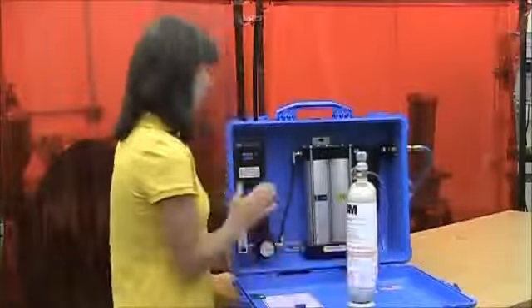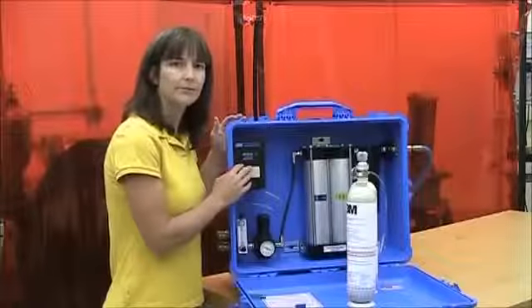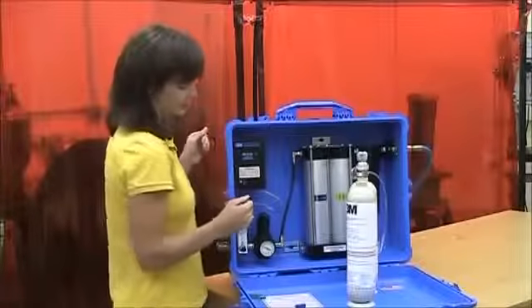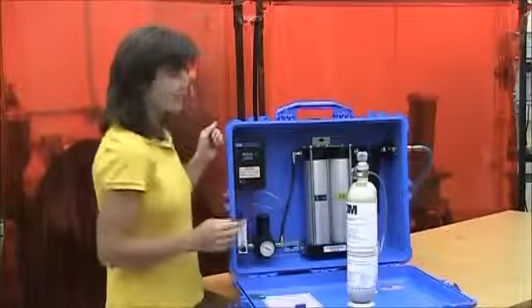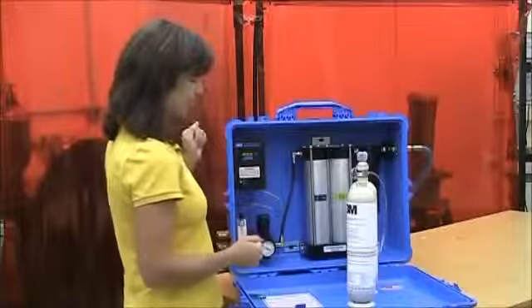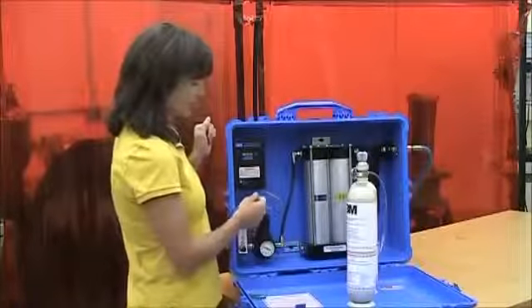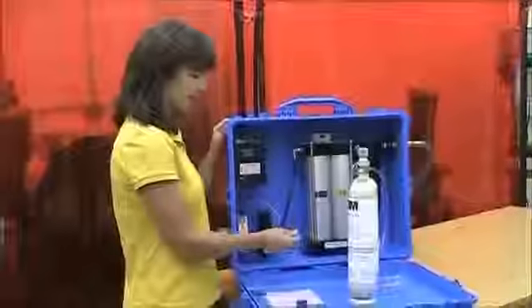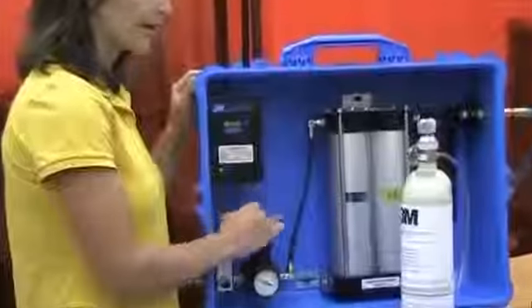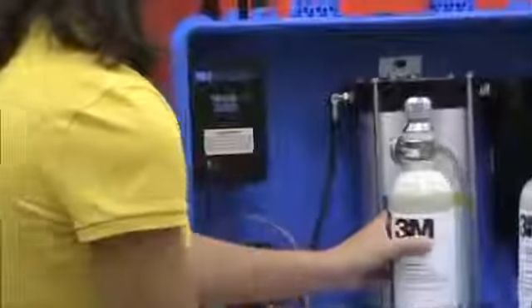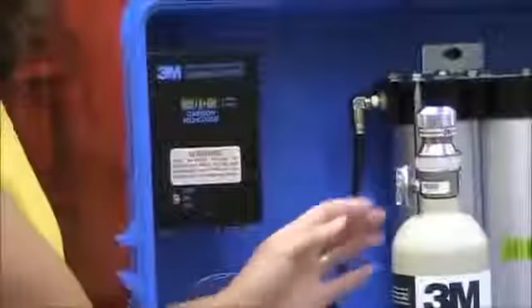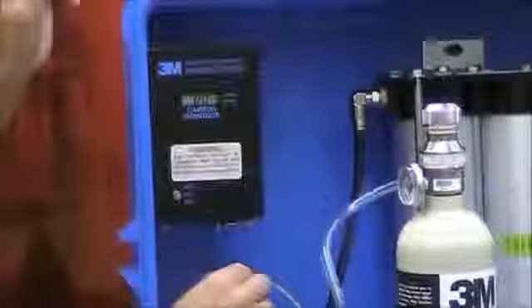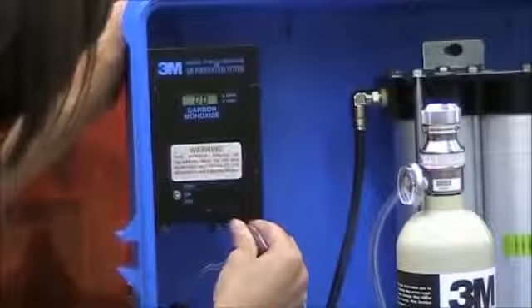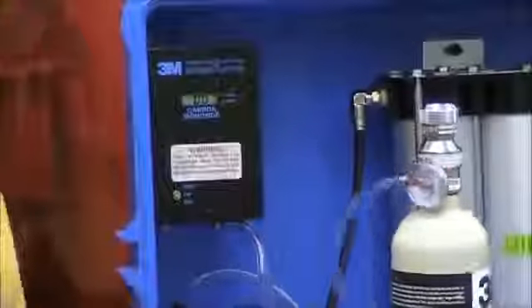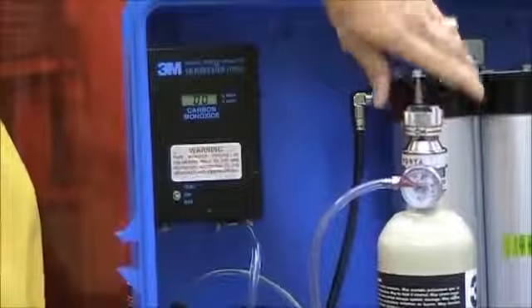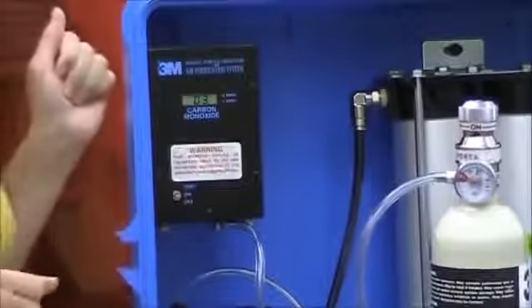You're going to want to make sure that the calibration gas itself is not expired. You also want to make sure your carbon monoxide monitor has been warming up for at least 5 minutes. This will help the calibration go a little bit smoother. Mine's been on for at least 5 minutes, so we'll get started. I'm going to take the tube that comes from the compressed air off of the bottom of the monitor. Make sure my regulator is attached to my zero air. And then I'll attach my zero air to the monitor. Turn my regulator on.